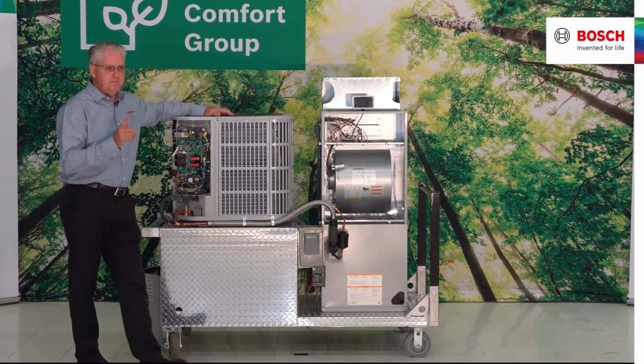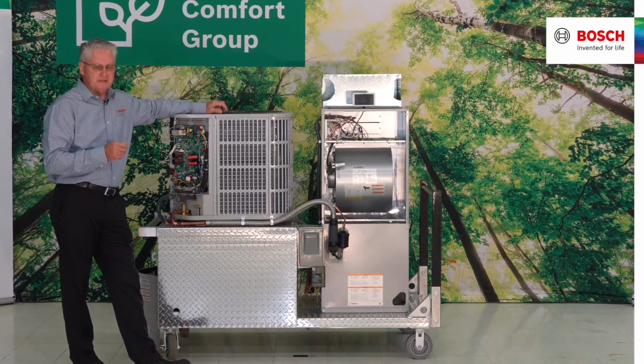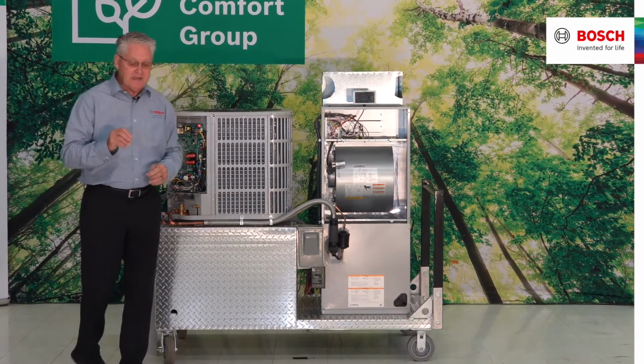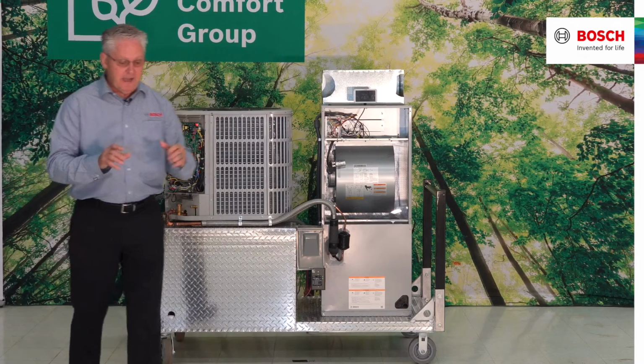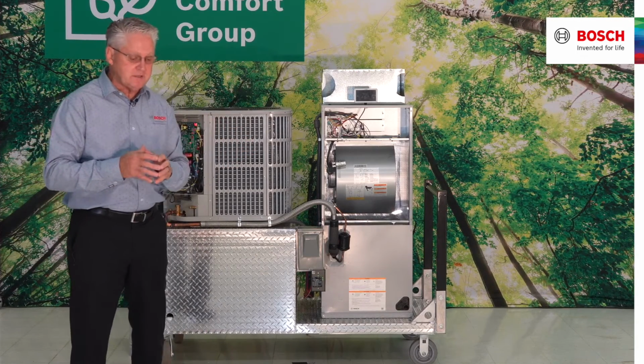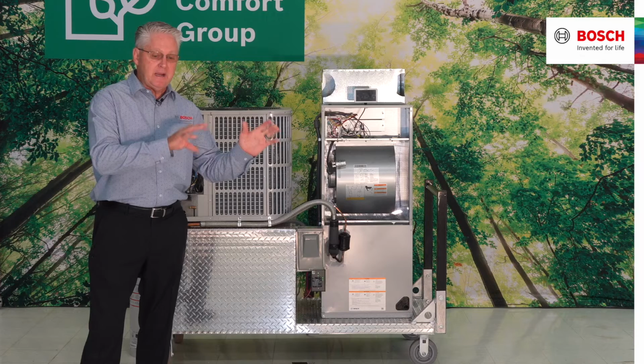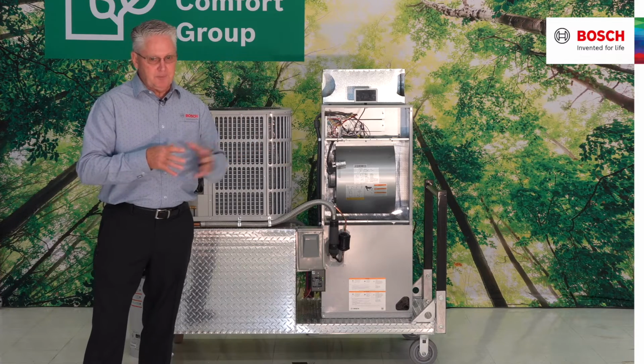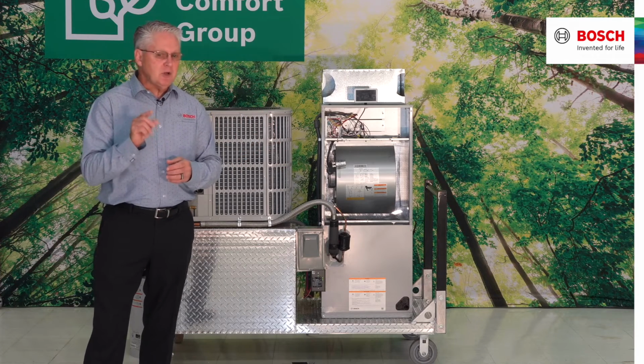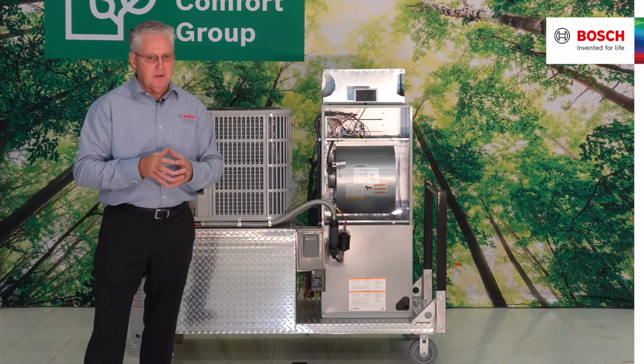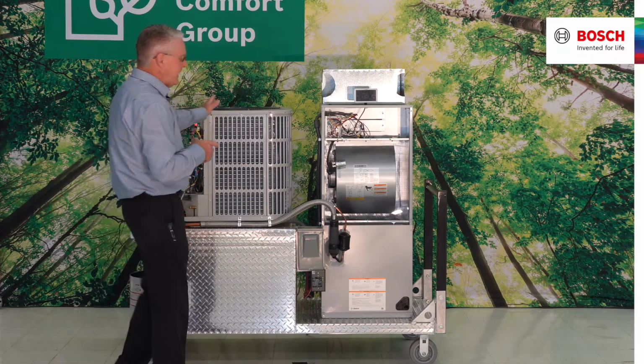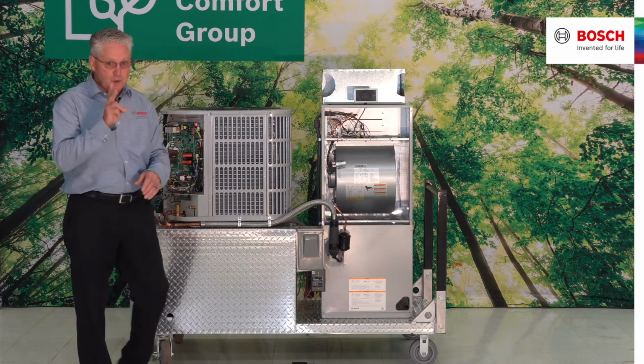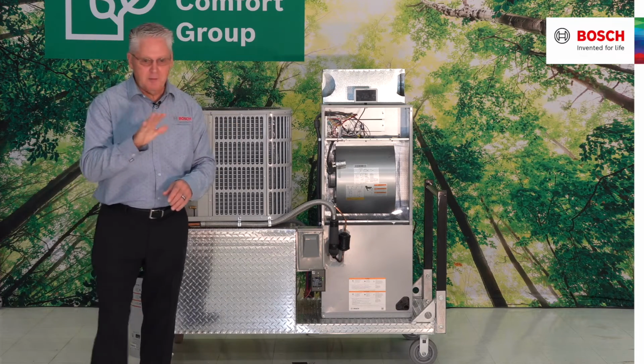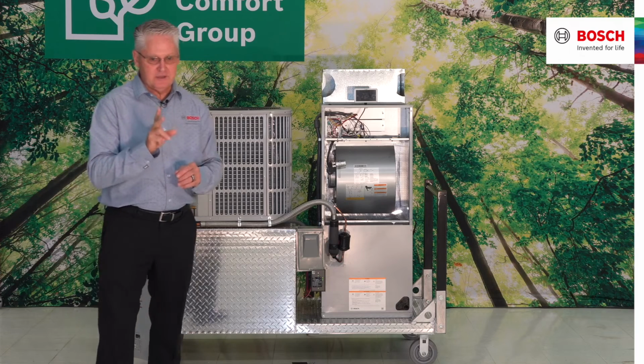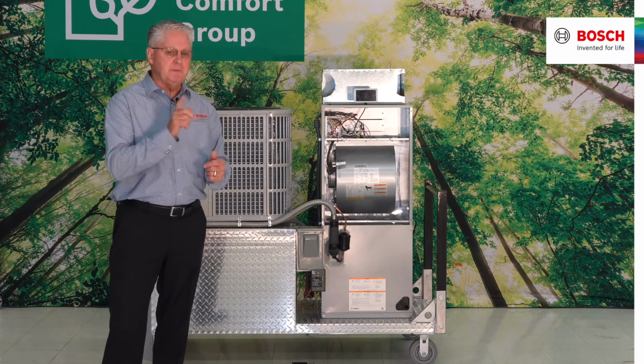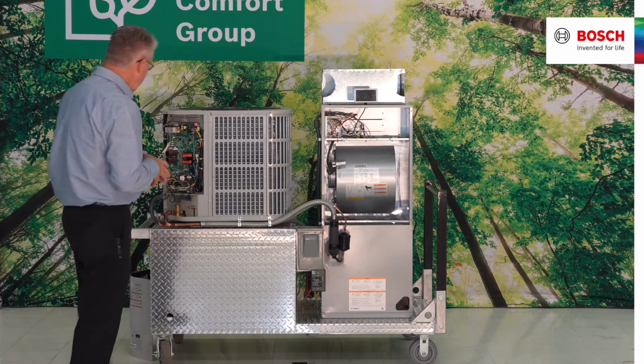This is a BOVB 036, which means that I can take this particular machine at 36,000 BTU capacity, flip J2, and make it a 2-ton application. Now, Bosch also has a dedicated 15 Seer 2-ton only. It cannot be a 3-ton. It is a dedicated 2-ton only. But let's talk about the BOVB 36.